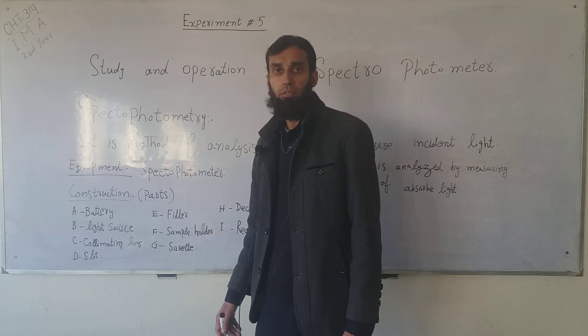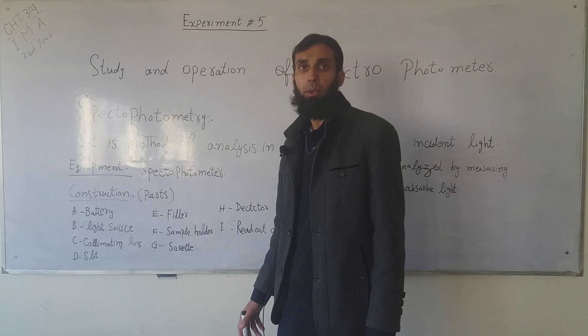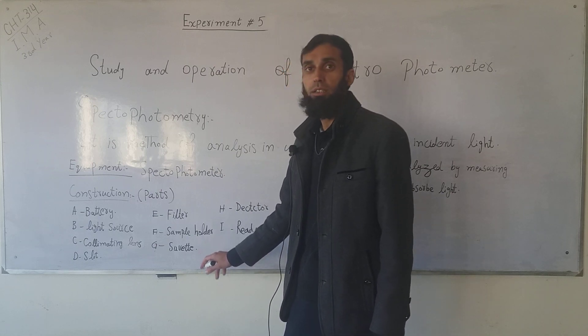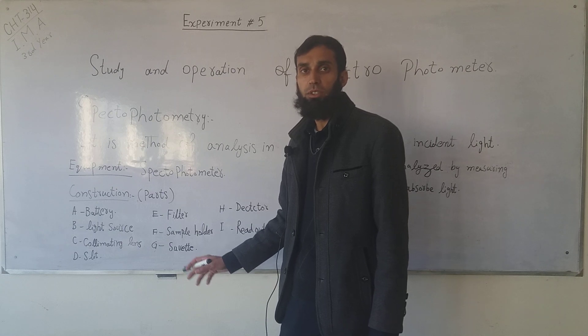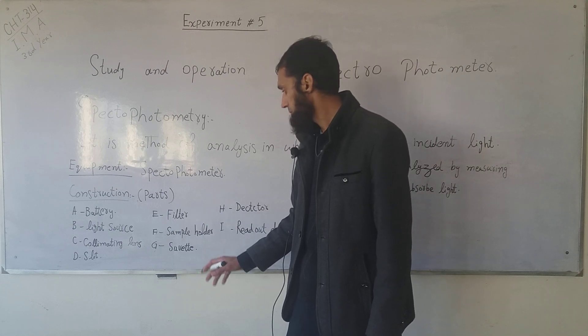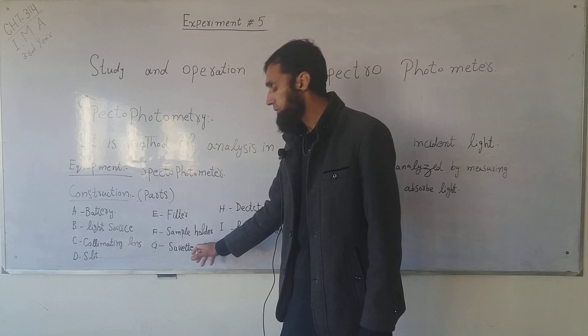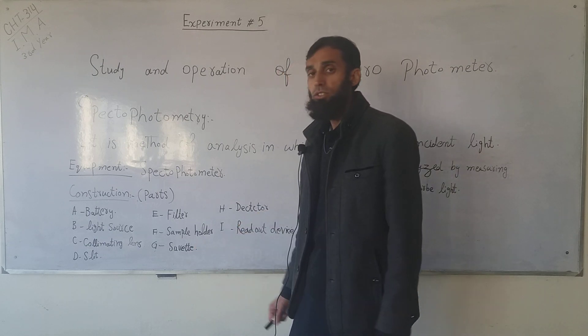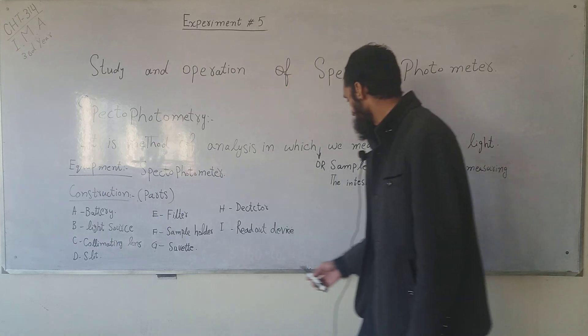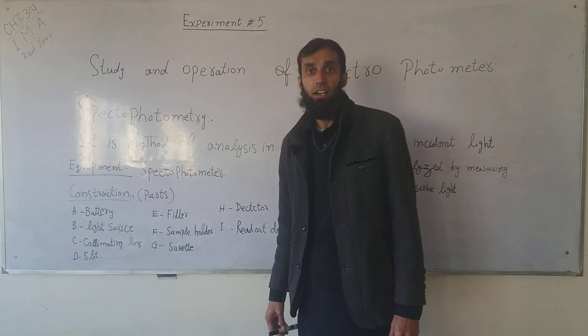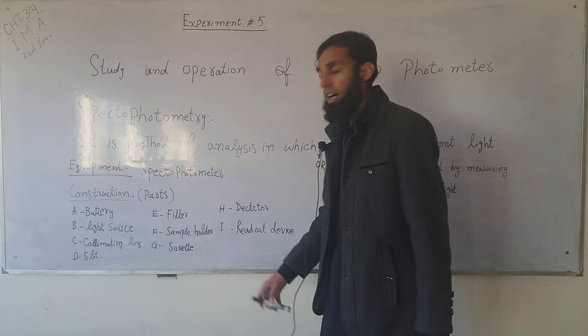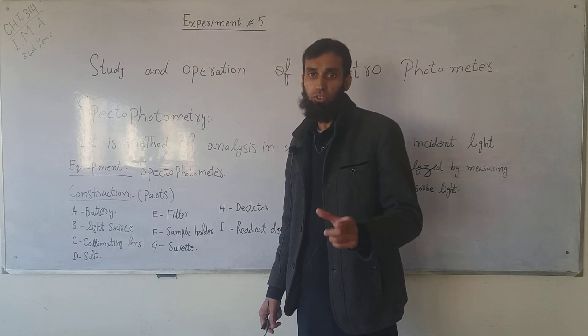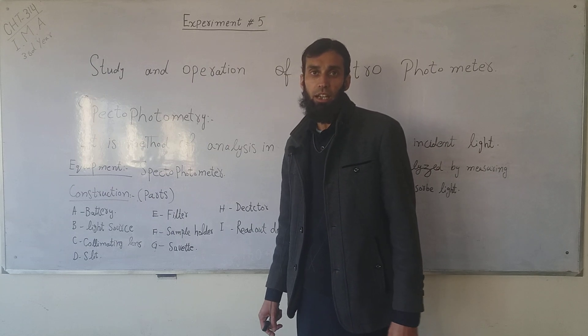Different wavelength filters can be used in the sample compartment. There is a sample holder, which holds the sample tube. The detector detects the incident light, and the current signal is sent to the reader. The reader shows the reading on an LCD display.